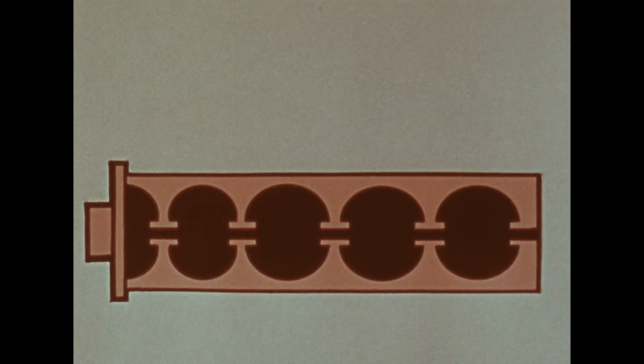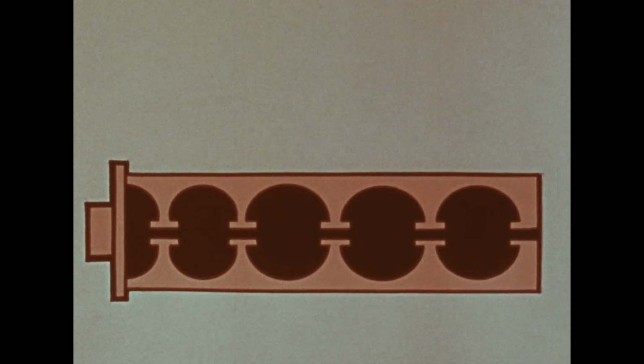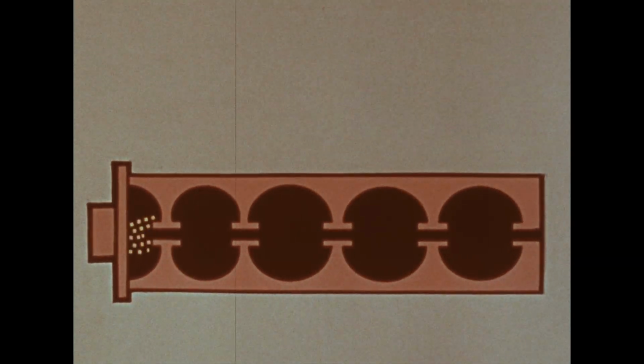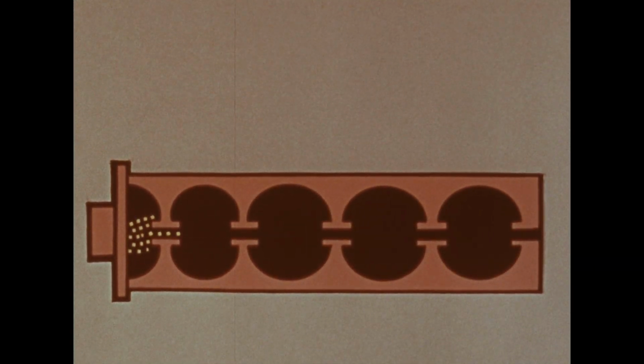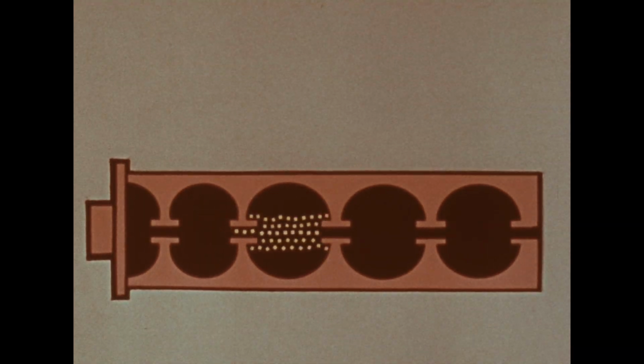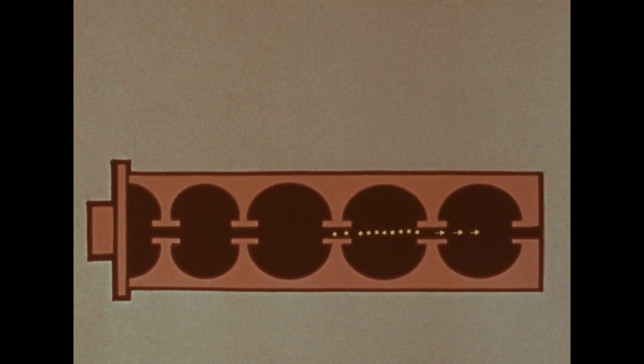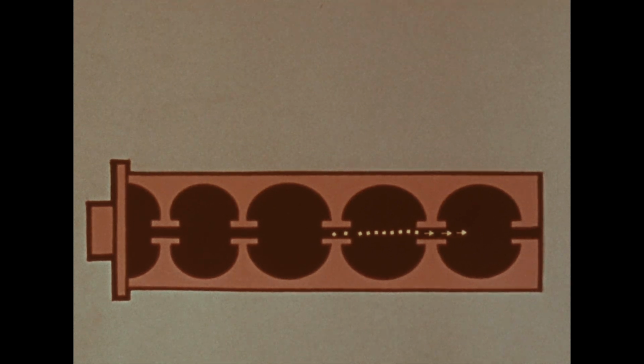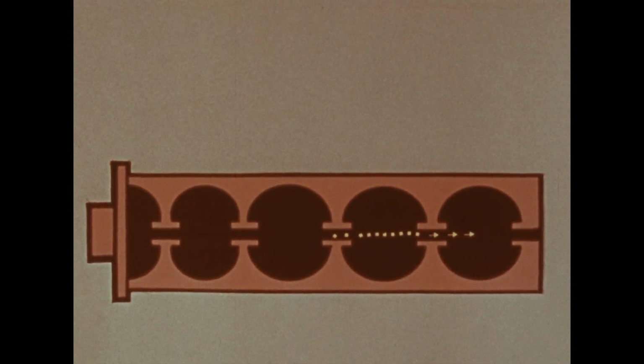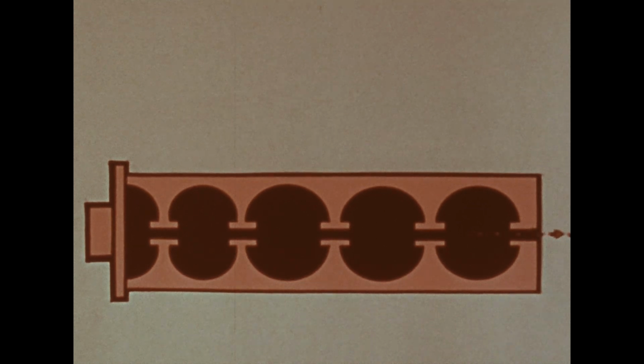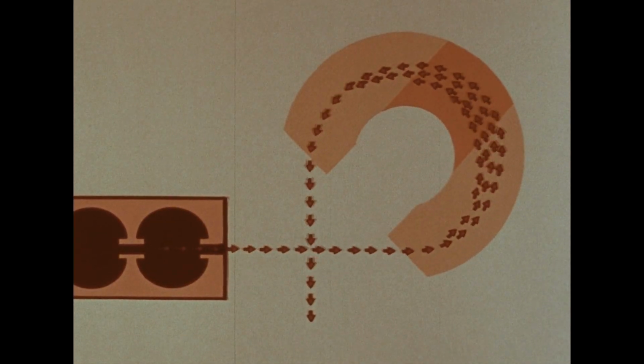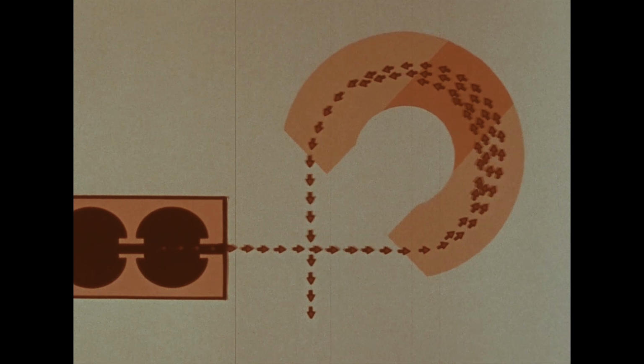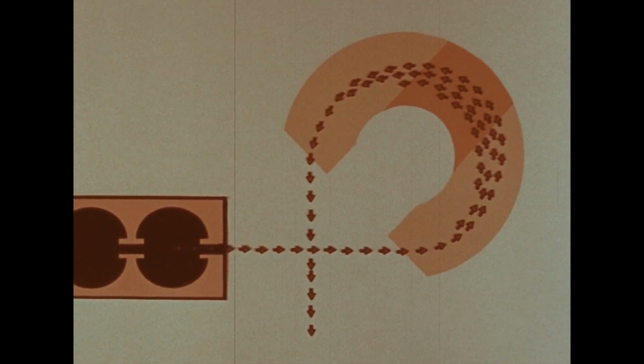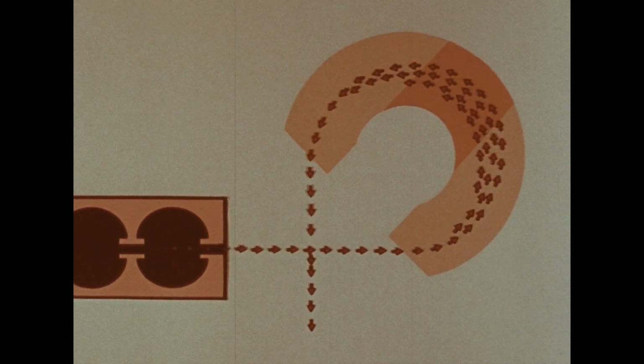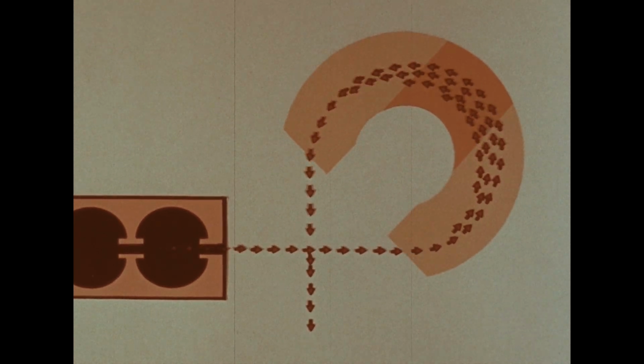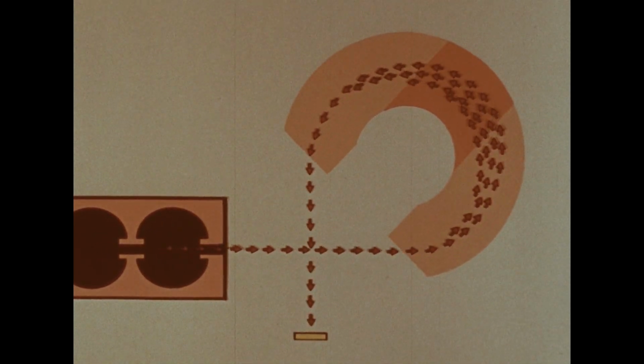The first few cavities of the waveguide form the bunching area. This area bunches the pulsed electrons and adapts their phase to the high-frequency standing wave. When these electrons are accelerated close to the speed of light, a high-energy beam with a narrow energy bandwidth is produced. The electron beam leaves the accelerating waveguide and goes into the achromatic bending system. This bending system filters out the electrons that are above or below the desired energy level, stabilizes the spot position of the beam on the compound target.